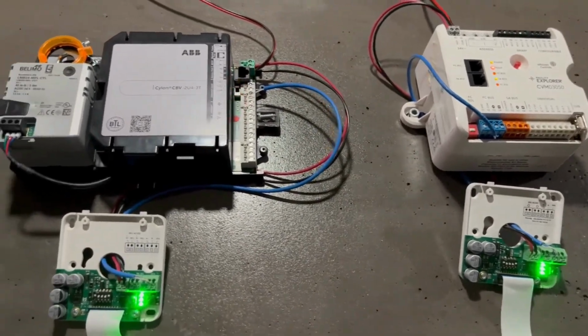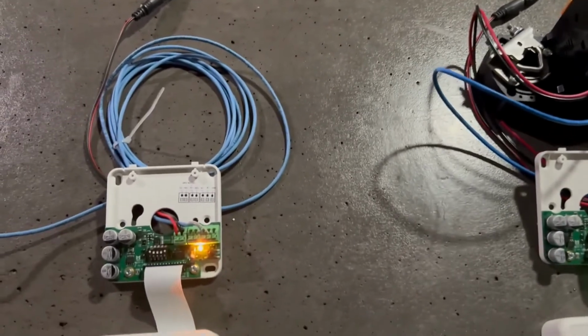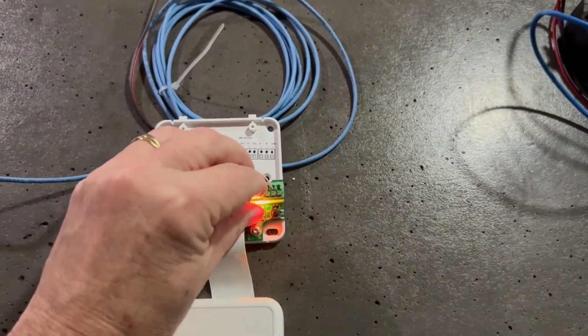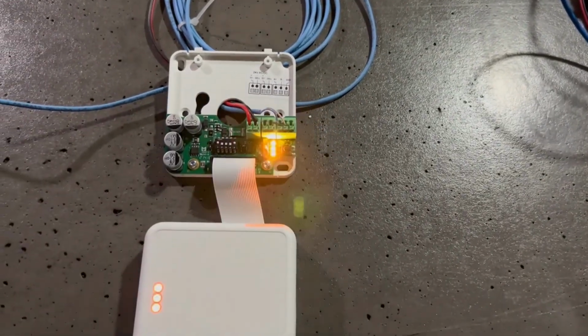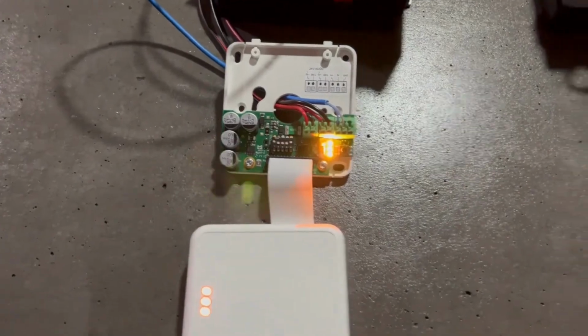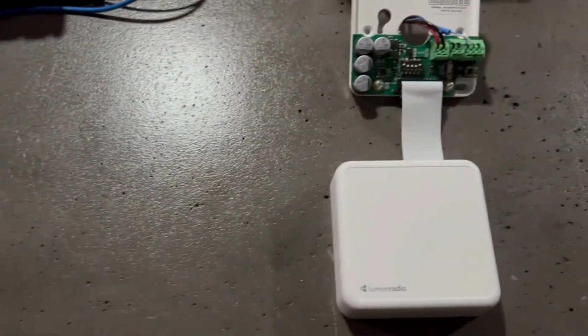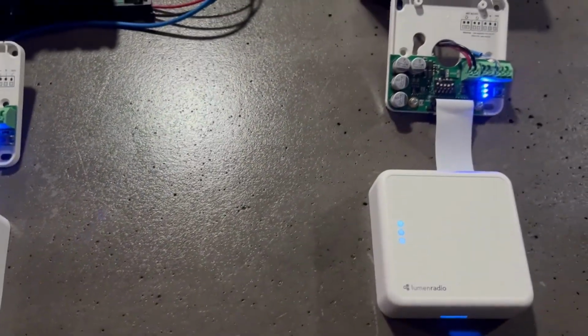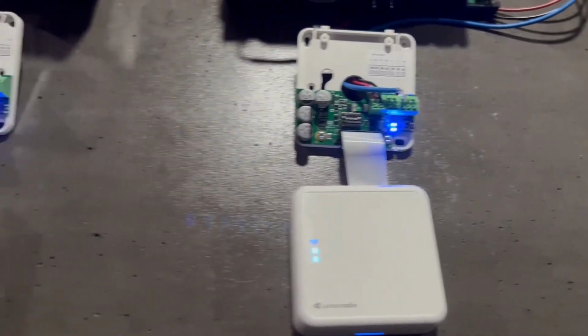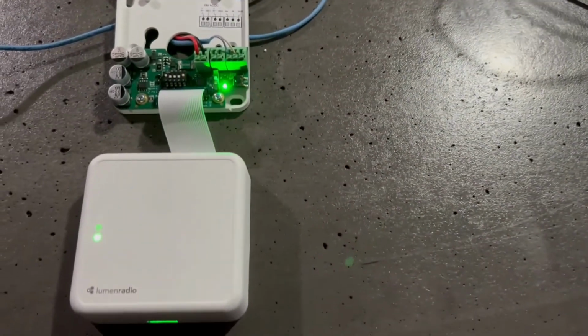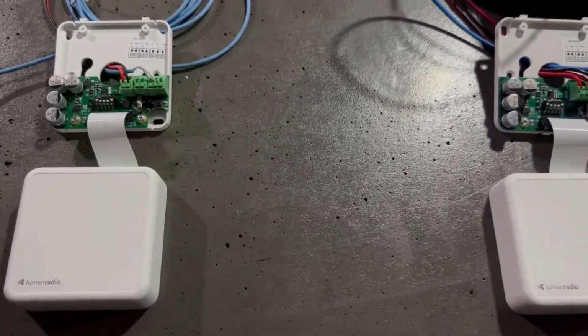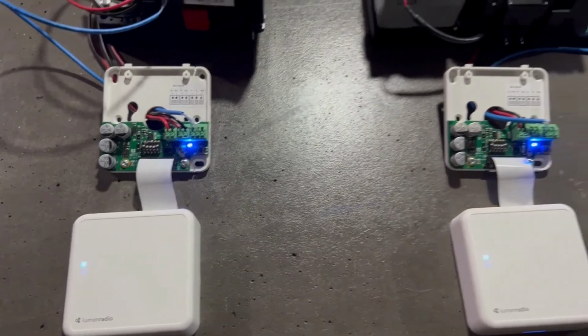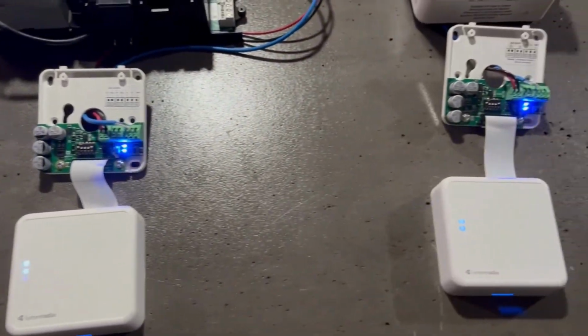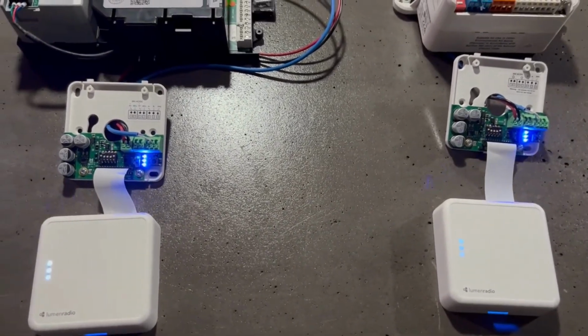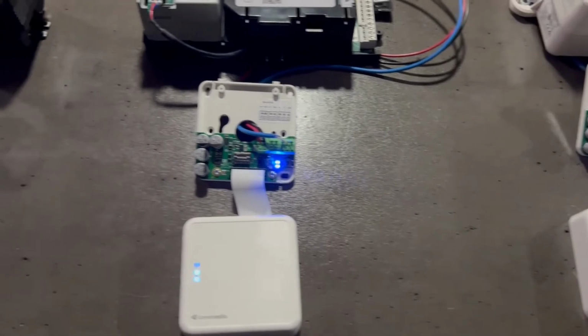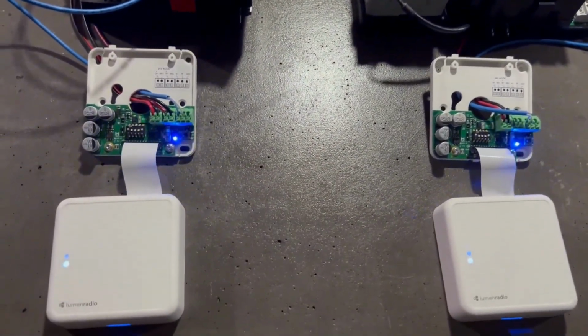Now, if all these were just powered up for the first time, what we do for commissioning and setting up the mesh is simply setting the dip switch on the gateway to the middle position for commissioning, and you'll see the LED sequence of each. First is starting out with 3 amber lights blinking, and then once it starts commissioning, you'll see the nodes have turned blue and are cycling through, and you will see the gateway is cycling through green, that it is setting up the mesh network with all of the node devices. As they become set up in the mesh, you'll notice the change in the LED sequences when it gets to that point. There you go.